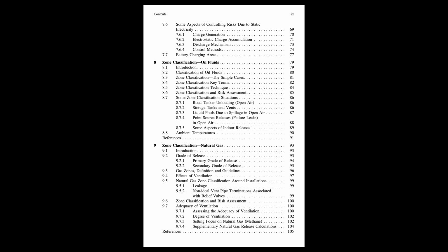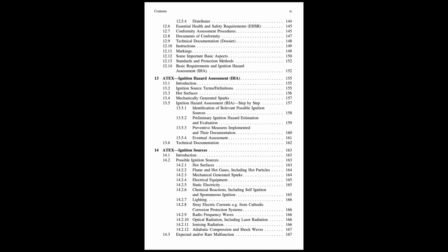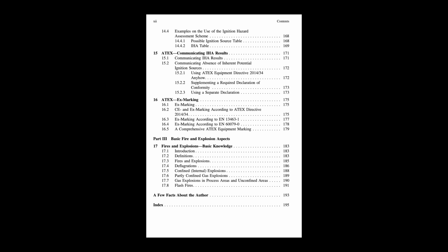Essentially, yes. The guide outlines 4 main categories for these mitigating measures. All right, lay them on us. What are the options when prevention isn't foolproof? Okay, first up is explosion relief venting. This involves designing specific weak points, often panels or membranes, into the equipment. Like a predetermined breaking point. Exactly. They're designed to burst open safely at a certain pressure if an explosion starts inside.